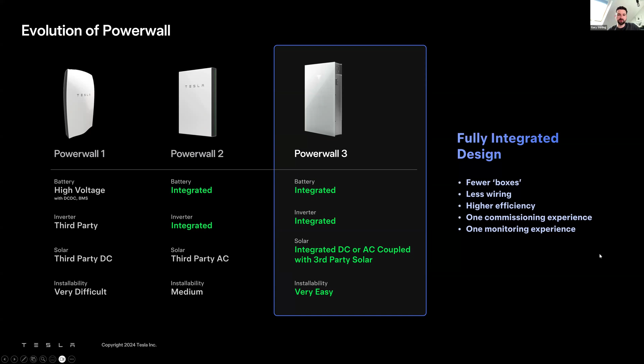Starting with power output, Powerwall 2 was only capable of 3.68 or 5 kilowatts of power. We've massively ramped this up with Powerwall 3 — you can still set it to 3.68 to meet G98 requirements, or set it to 5, 6, 7, 8, 9, 10, and 11.04 kilowatts of power. So a ton more power in a single unit, reducing the need for multiple units.